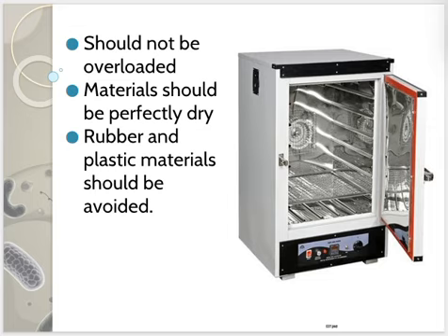When using a hot air oven, certain precautions are important. Avoid overloading the oven because it can block heat circulation and reduce effectiveness. Material should be completely dry before sterilization, as moisture can interfere. Also, avoid rubber and plastic items since they can be damaged by the high temperatures. Following these guidelines ensures the sterilization process works as intended.